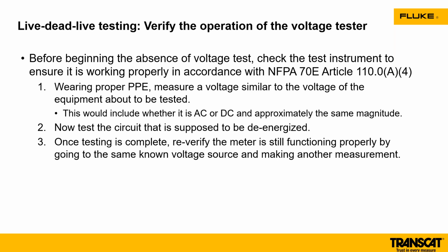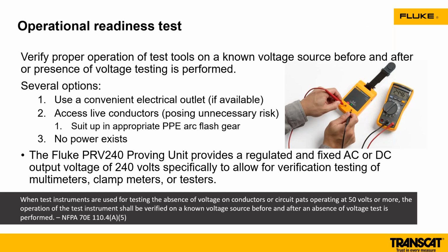Now, a lot of people are going out to job sites where they don't have a known voltage source. Maybe there's a voltage drop, something of that nature. They don't necessarily even know what the voltage may be. So how do you know you have a known voltage that you can test against? What we also have is a proving unit. Get out there and use a proving unit. This allows you to quickly and easily, at your truck or wherever that may be, even on the site, properly do a live dead live test on your meter and validate that it's working correctly.